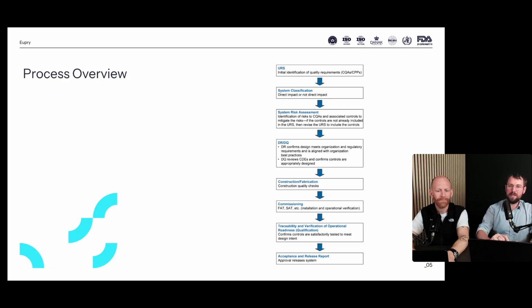Then you would often follow with commissioning, so either a FAT SAT check, often for standalone units, but we also see a lot of customers replacing this with an installation qualification, ensuring that it's installed. So if you have a warehouse, as an example, we've identified user requirements, we've identified the plans for how to make sure that we can store goods at, let's say, 2 to 8 degrees. Then we first try to verify that the equipment we've installed and which we've reviewed is installed as it should be and per specifications. And then we start doing the verification of operational readiness or qualification. That would typically involve our mapping, but it can also involve other qualification steps. And then after that, we would do a release. But today we're going to focus on the user requirements, because that's really the baseline for being able to perform a mapping, to be able to perform qualification or verification of these individual items.